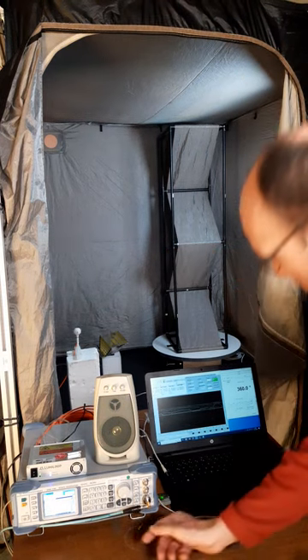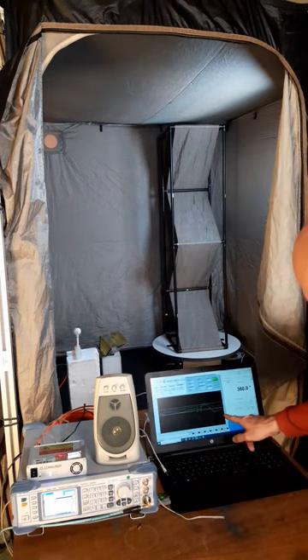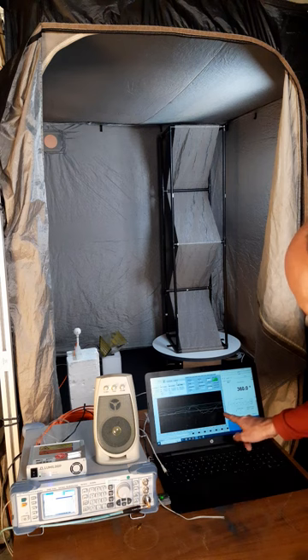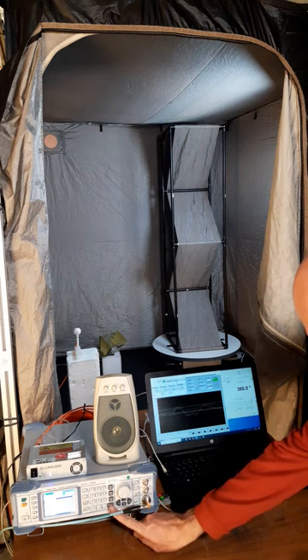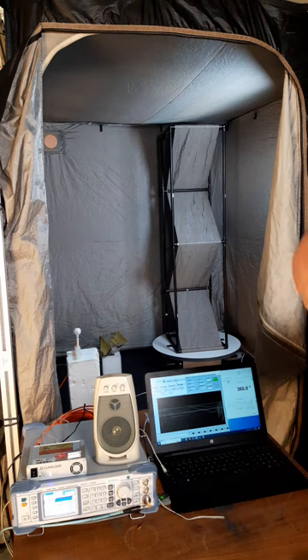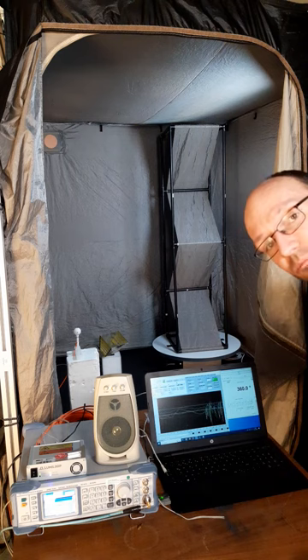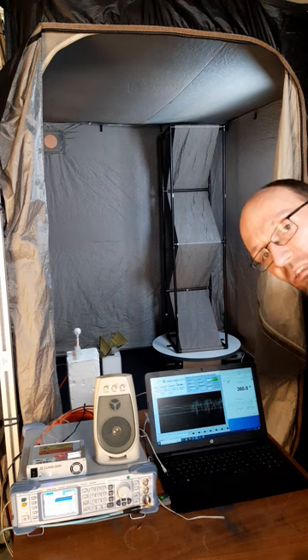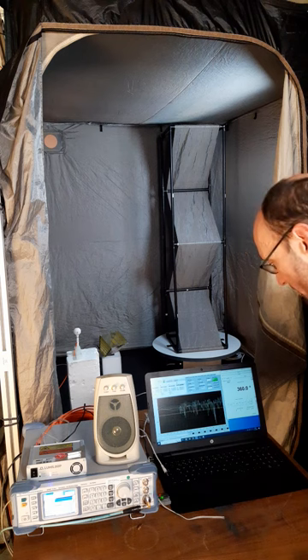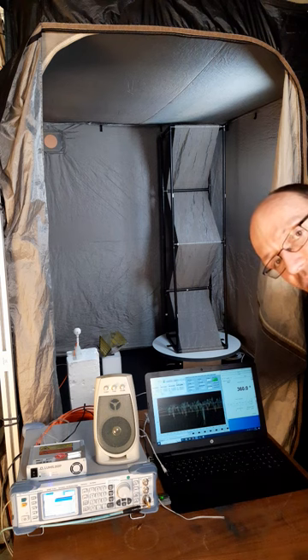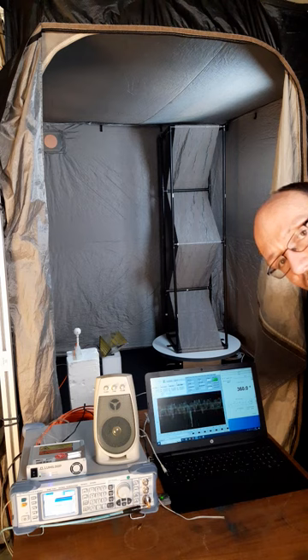So if I enable it, once again we have more or less steady values here now. If I enable a frequency sweep, now the frequency changes by 1 megahertz every 10 milliseconds. You see how the field rapidly changes inside this reverberation chamber. This would be called frequency steering.